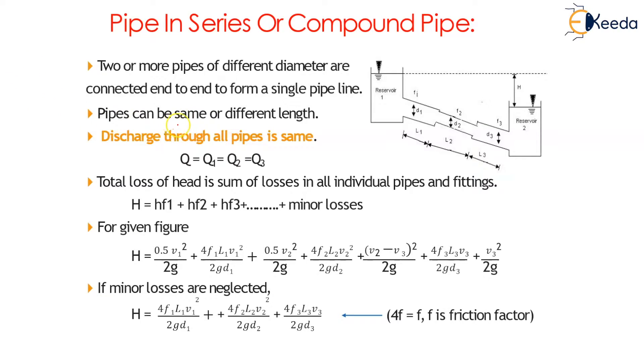These pipes can be of the same or different length. As seen in the image, there are three different pipes having three different lengths: L1, L2, and L3. Discharge through all the pipes is the same: Q1 = Q2 = Q3 = Q. Total loss of head is the sum of losses in all individual pipes and fittings, so total head loss H = HF1 + HF2 + HF3.